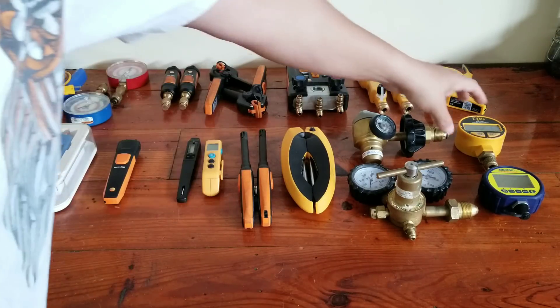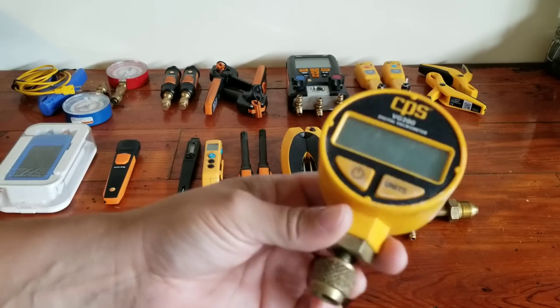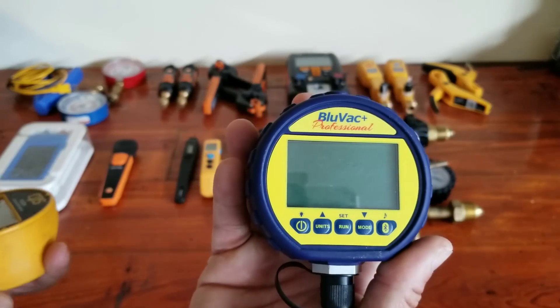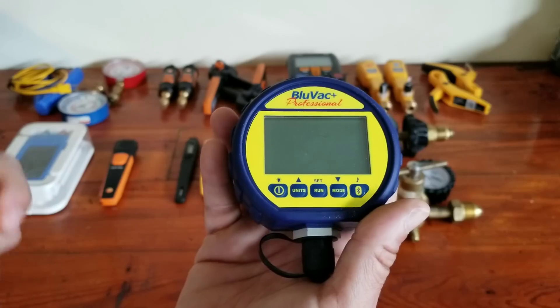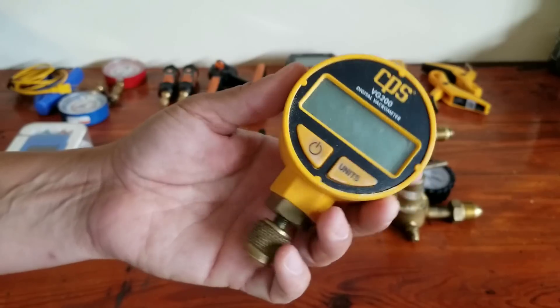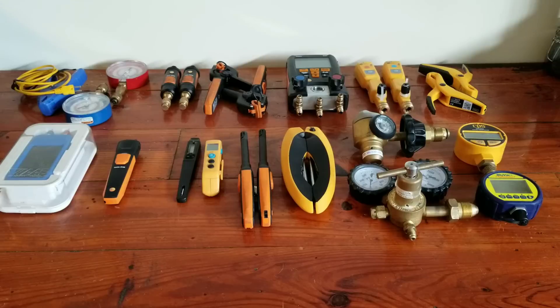And lastly up here, I just have a couple micron gauges. Just a very basic CPS digital micron gauge — accurate, inexpensive, and gets the job done. Then on the opposite end of the spectrum, you can go to something like the BluVac Plus Professional, which is going to give you a whole lot more bells and whistles. You can use an app, record the data, trend the data, that kind of thing. It's definitely not something that's required. I know a lot of guys, including myself, swear by it — it's a great gauge. But I used the CPS for well over five years and had no issues at all. Very accurate. As long as you're using the tools you need to do the job properly, I'm not very concerned with the particular brand that you're using.